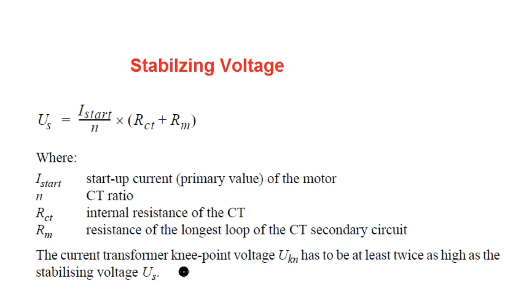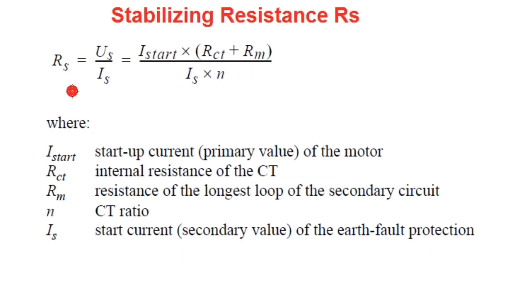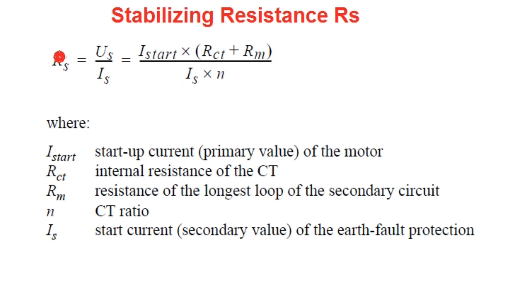We must check whether the knee point voltage Ukn is greater than two times the stabilizing voltage Us, to verify CT requirement fulfillment. Once Us is known, the stabilizing resistance is calculated as RS = Us / Is, where Is is the relay setting current — the start current of the earth fault protection. So RS = (Istart × (RCT + Rm)) / (Is × n).